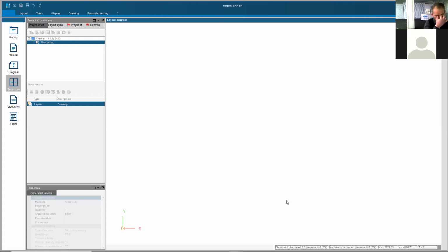If you're working on smaller distribution boards and you prefer an IP65 rated board, you can then select the different classifications. If you want, you can go up to IP65. And obviously, if you select the IP rating, it will drop off some of the distribution boards that won't be able to do that. IK rating is, I also want to say, the strength of the distribution board. The Quadro Plus is IK10 rated, which is very, very strong and very robust, and can handle a huge amount of impact.